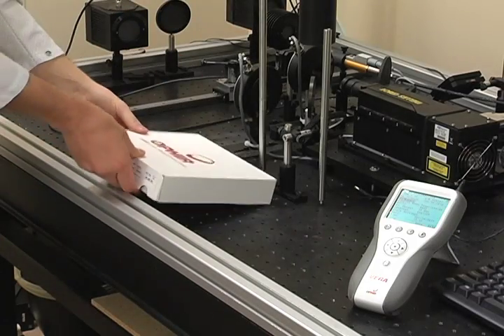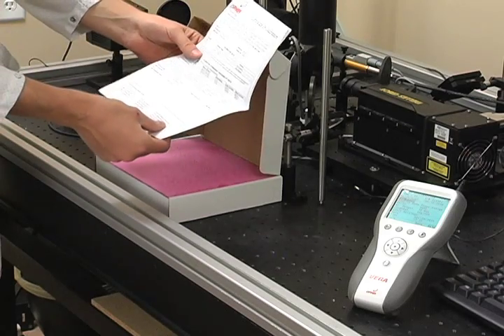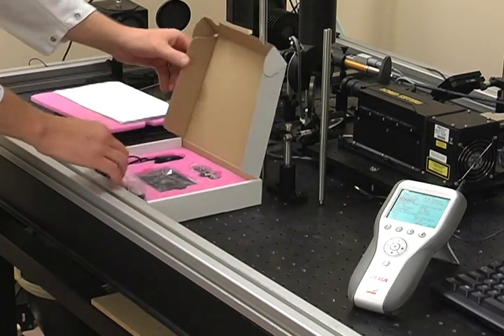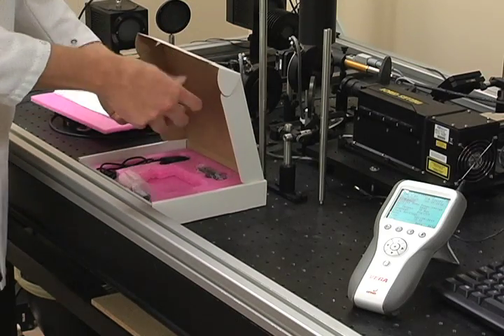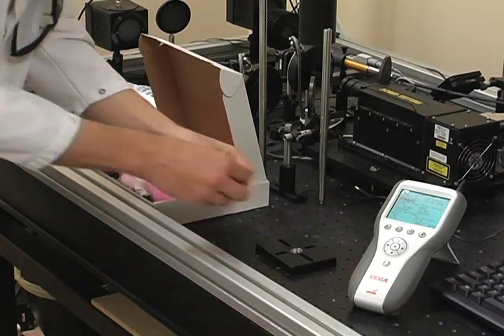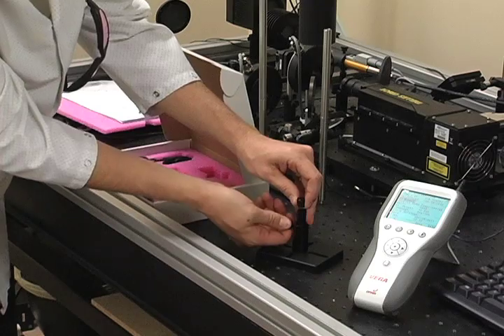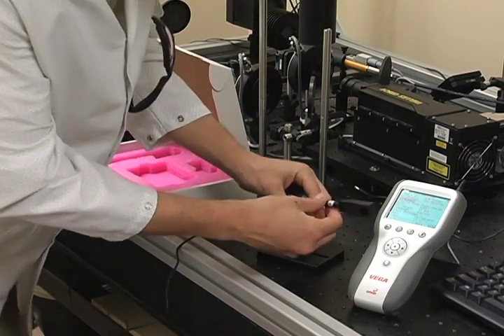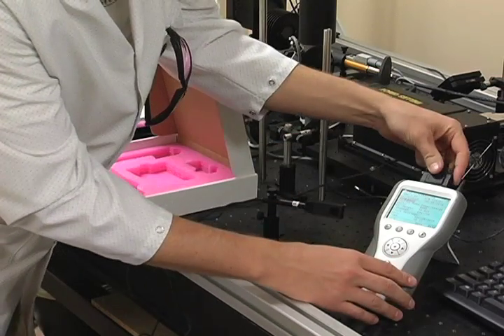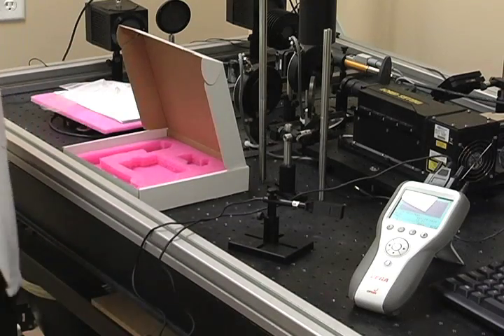In our first demo, we're going to show a PD300 photodiode sensor connected to a Vega meter. First, we assemble the base. Screw the post into the sensor head, and place the sensor so that the center is aligned to where the expected beam will be.